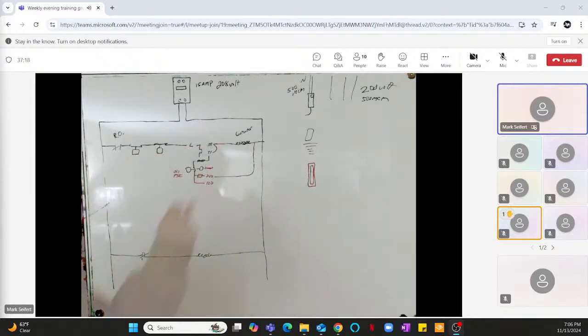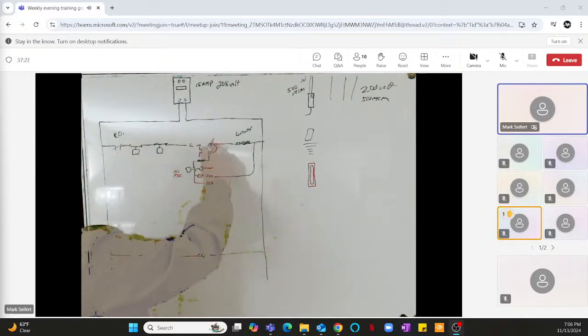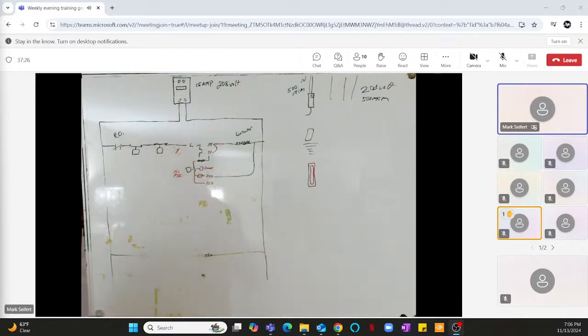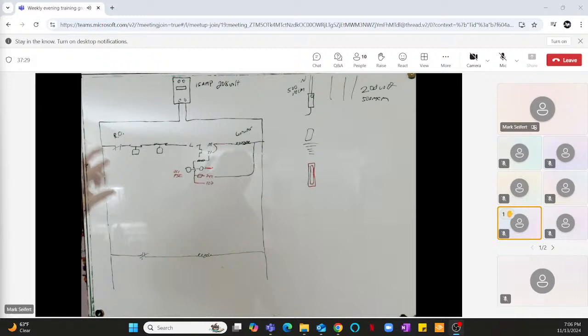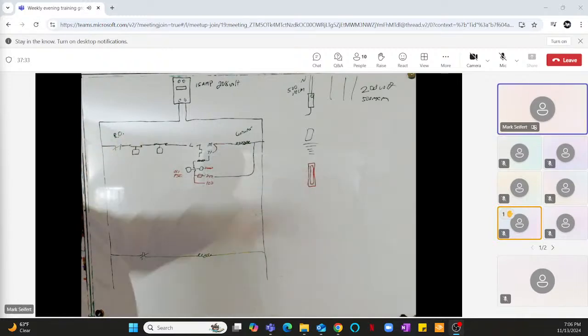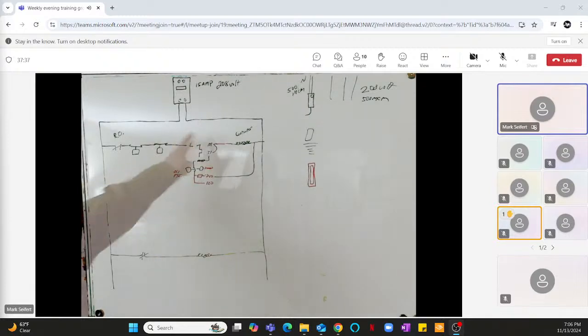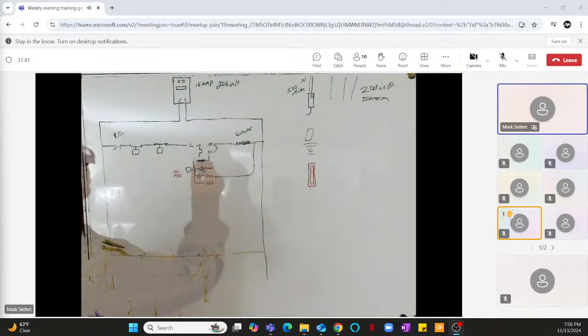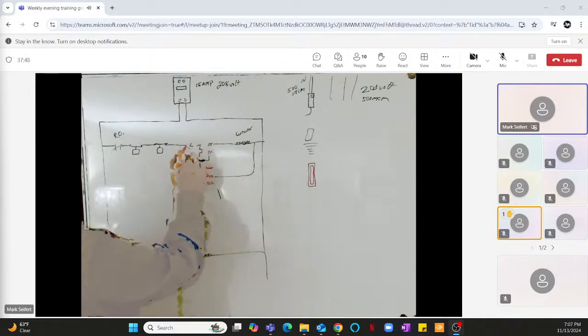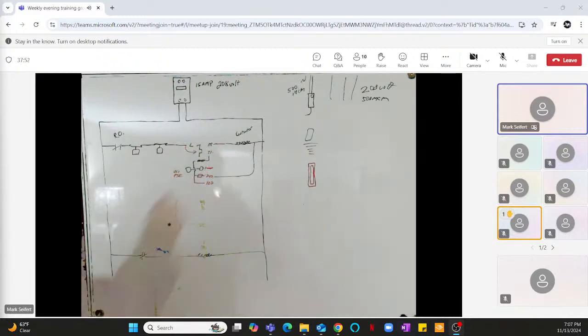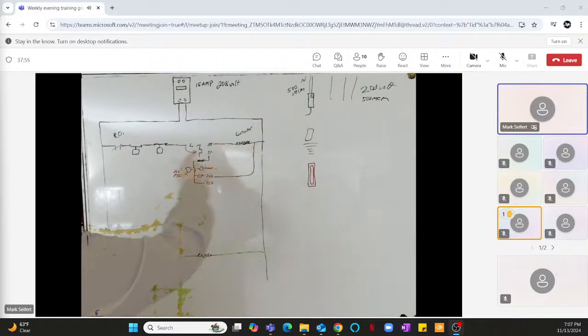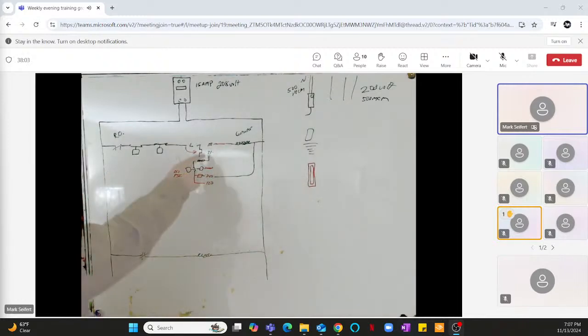If it's got power all the time, let's just say for some reason these wires were crossed up, which you could find. If you find one of these things that's on all the time, and you try to reset it, but the little resistor is hot, it won't reset. The problem is going to be the M and L are crossed. A little troubleshooting guide. Imagine if you had L over there at T1 and it tripped. Yeah, it's going to shut off the contactor, but it's still going to power up this heater circuit and also this resistor. Because it's not going to have oil pressure, it's going to constantly have this feed here. And so you go to reset it, and it won't reset.